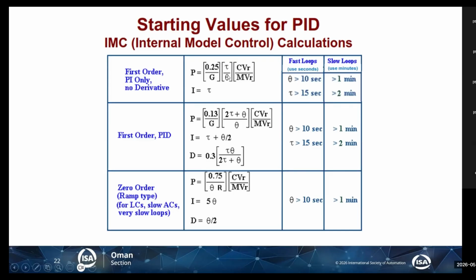Multiplied by tau over theta, where tau is the time constant and theta is our dead time or time delay. Multiplied by the CV range. Like in the first example, I'm in a furnace and my CV is temperature, so I have to see that temperature range, for example from 200 degrees to 300. Then divided by my MV range, typically from 0 to 100 if it is a valve. The result of this equation will be my optimum proportional gain. And integral will be equal to tau. I calculate tau and use it as integral.